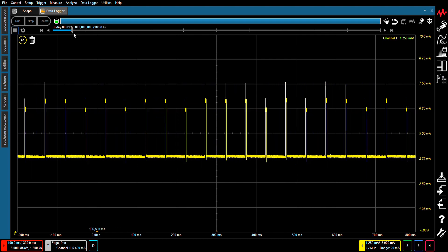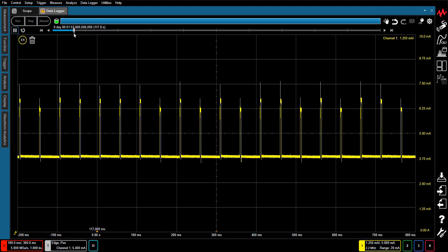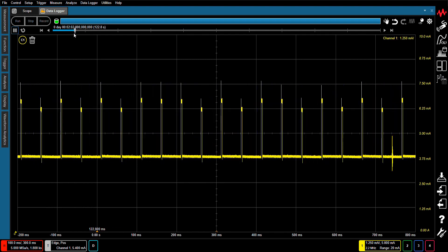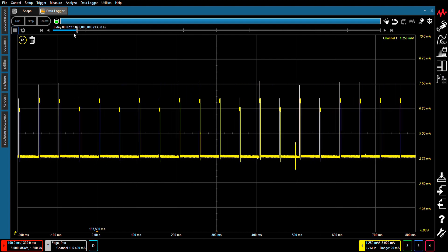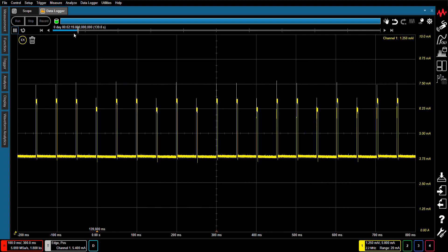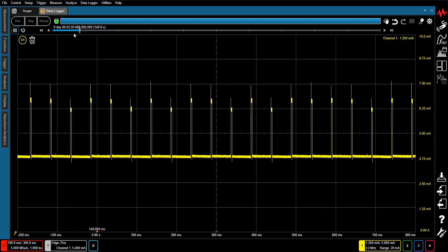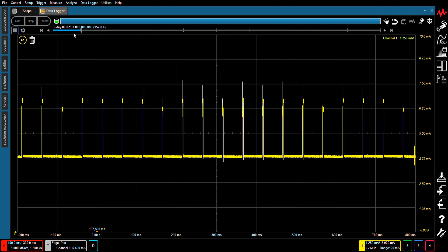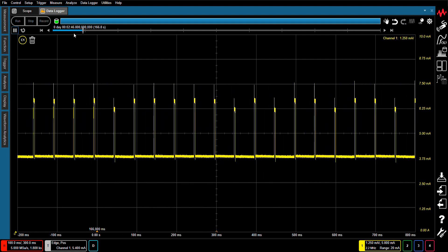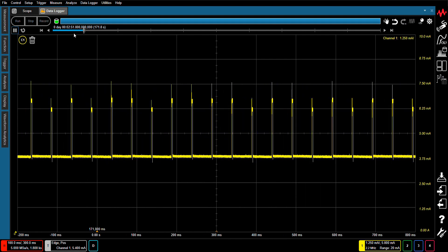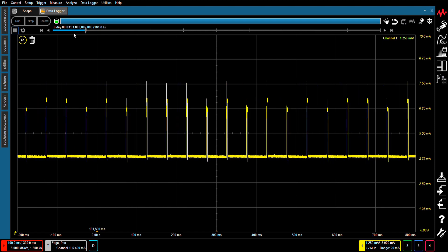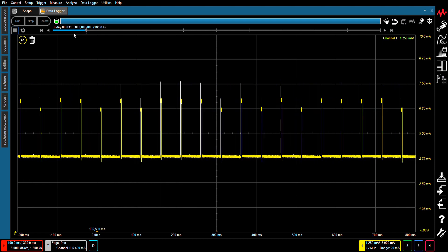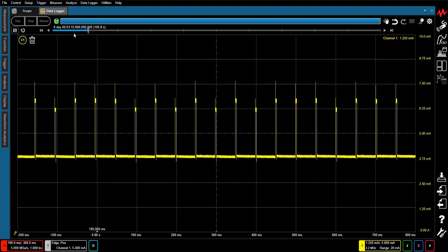The CX3300 and its data logger option allow the uninterrupted recording of long duration waveforms to enable the detection of anomalous waveforms. This is not possible using a conventional oscilloscope due to the scope's limited memory depth and dead time due to intermittently triggered measurements.